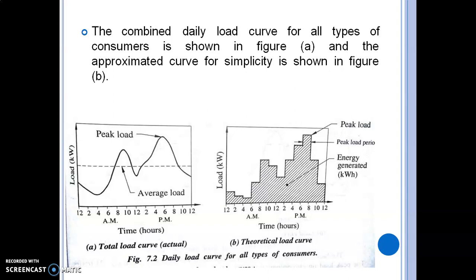The area under the load curve represents the energy generated in the period under consideration. The energy consumed by the customer is given by the integral from 0 to 24 of the load in kilowatts multiplied by dt. The average load of the power station is obtained by dividing the area under the load curve by the total number of hours — that is, 24 hours for a daily load curve.